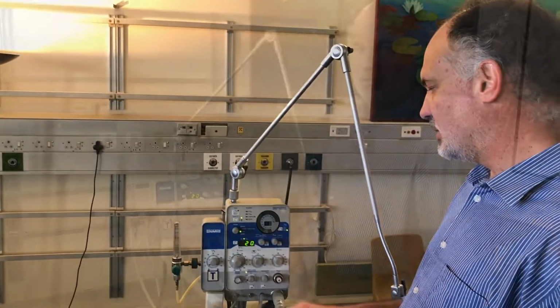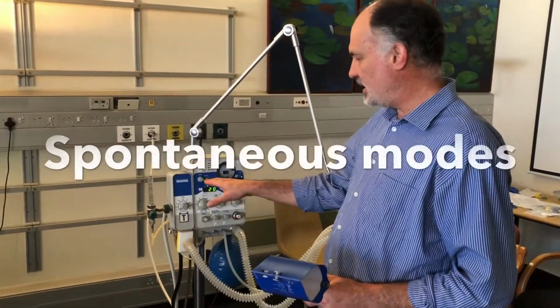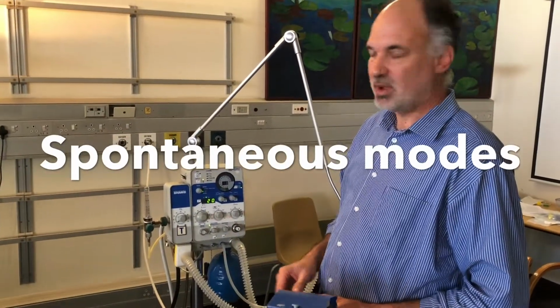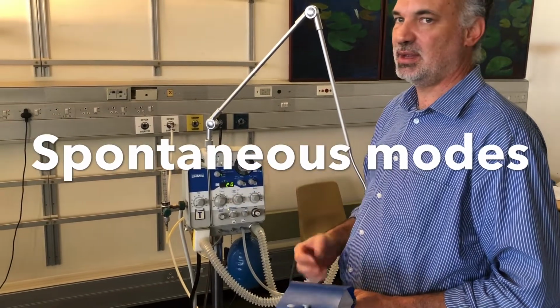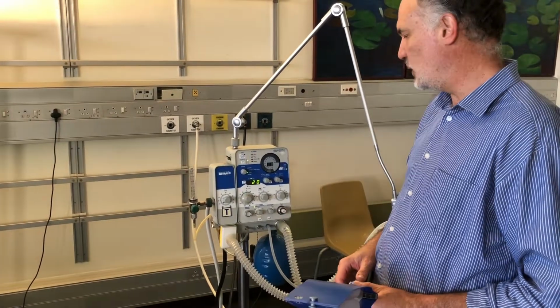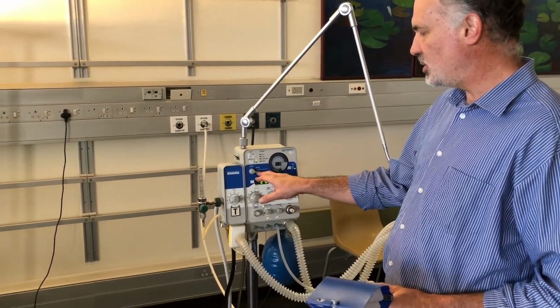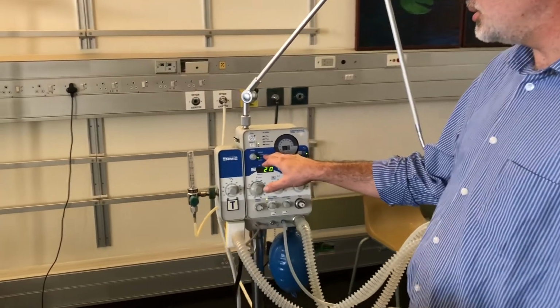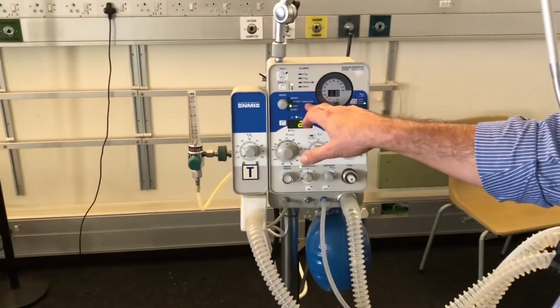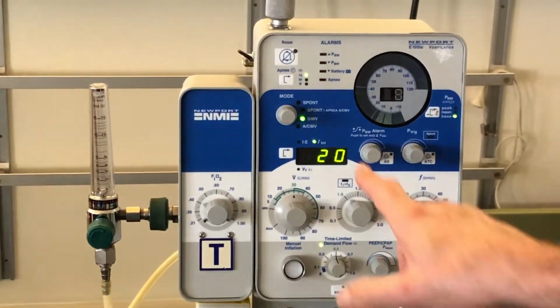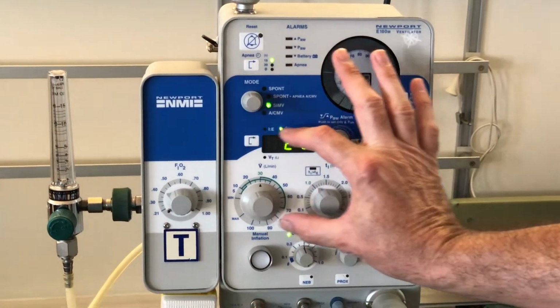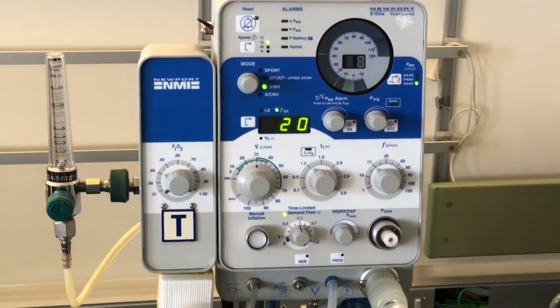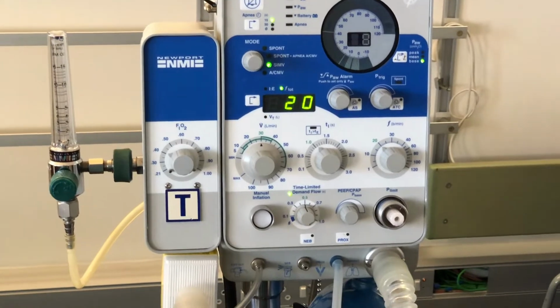All right. We're going to shift then from the setting of SIMV to the spontaneous modes. There are two of them. The first one, spontaneous mode with an apnea assist control backup, and the second one, just spontaneous breathing. So I'm going to shift the selector in a moment to go into spontaneous with apnea assist control backup. And just to say that the backup breaths then would be delivered as preset breaths in the other mode.